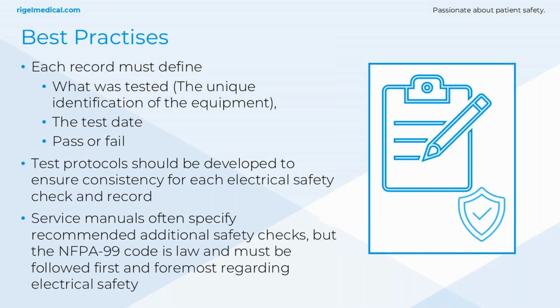They only need those minimum requirements of the test date, whether it passed or failed, and the asset ID of the equipment. So it's fairly loose on what the actual documentation required is. However, in most cases, the test results are still recorded. But in some states, I still see it now, where just a pass or fail record is needed, and that's where a product like the SafeTest 60 Plus really comes into its own.